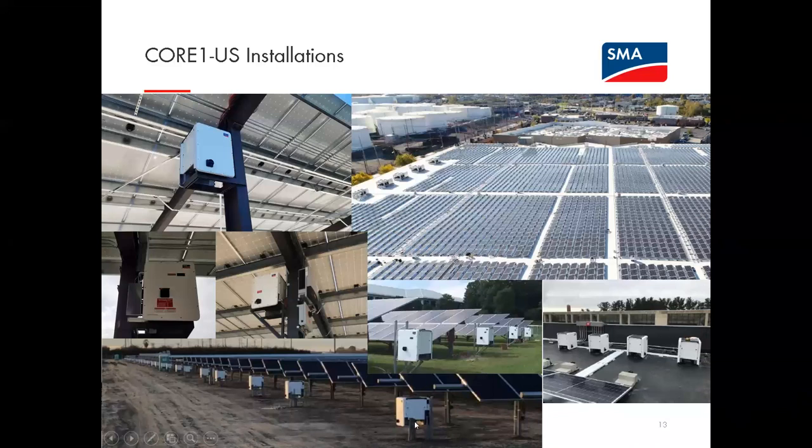But then you can see certainly for ground mount, you may have to raise these up off of just a concrete pad to be over the elevation of the floodplain. So again, you have access to those threaded screw holes in the bottom of the body of the inverter to attach whatever mounting structure is reasonable. The one thing that would be a requirement is I believe you have up to a 3-degree tilt on this orientation, but otherwise vertical. That's outlined in the manual, but you have definitely flexibility in terms of what this mounting bracket and the mounting height would be. Yeah, definitely.